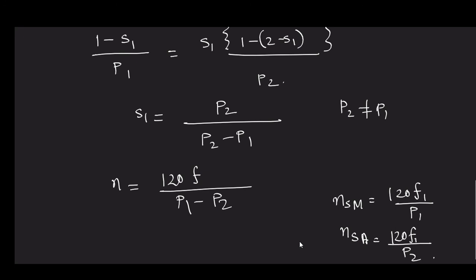What slip power you are supposed to waste in terms of rotor heating, instead of allowing it to heat the rotor, you are actually taking it out. Now, if you are taking it out, then what will happen? This power you are feeding to another machine that is also running in the same direction, and therefore that machine tries to rotate in the same direction, and these two machines act together to share the load, and that is cumulative mode, and you can easily vary your speed.